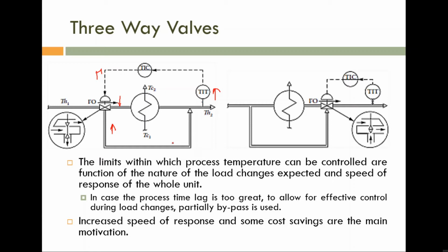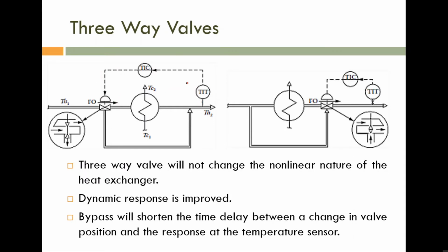Is it okay? So this is the process of the control of temperature using three-way valve or bypass line. I told you what the advantage is. By using three-way valve, the dynamic response is improved. But please note, this holds if the process has a large load effect and large time lag. Otherwise, the dynamic response is degraded.